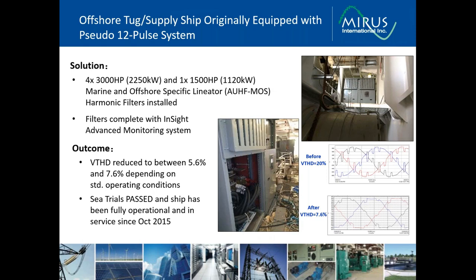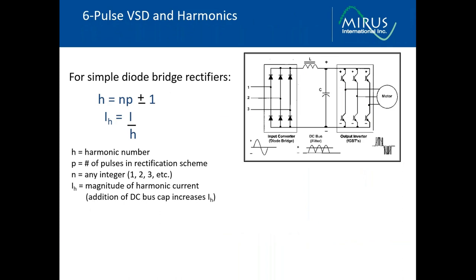With the filters installed, even in the most heavily loaded operation on dynamic positioning, voltage distortion was well below the 8% requirement for the marine certifying body, and they easily passed their Sea Trials, and the ship has been fully operational since October of 2015. So let's have a look at the harmonics generated by variable speed drives and review the various options for mitigation.